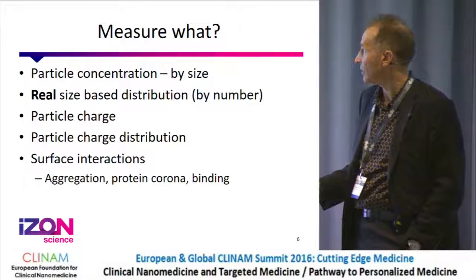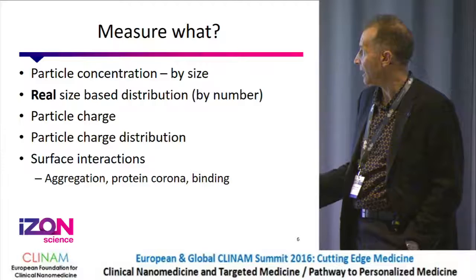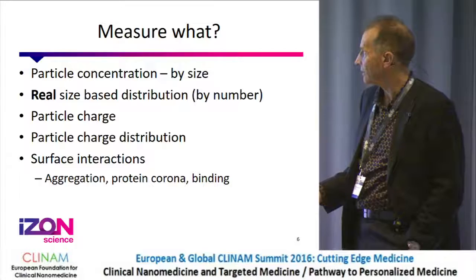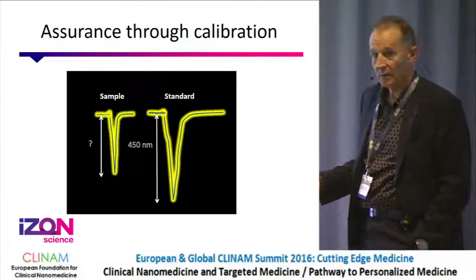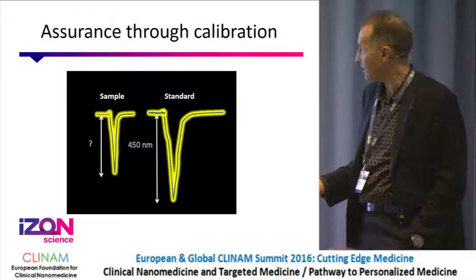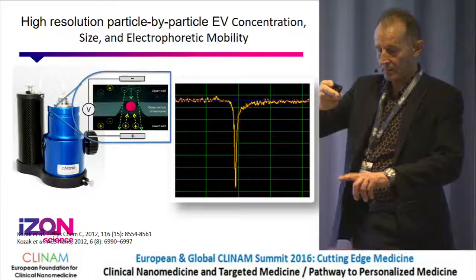What do you measure for nanomedicine? The particle concentration needs to be by size, not just a number. The real size distribution. Particle charge — and now it's relatively easy to get particle charge distribution — and then you can use that to understand surface interactions, somewhat similar to the last couple of speakers. Everything needs to be calibrated so every measurement is compared with a standard.